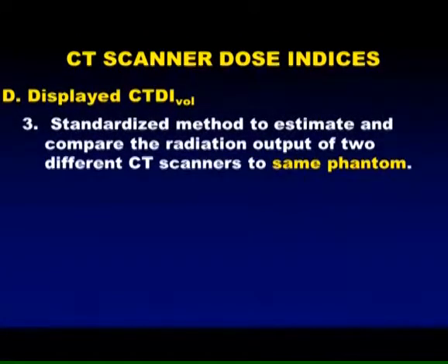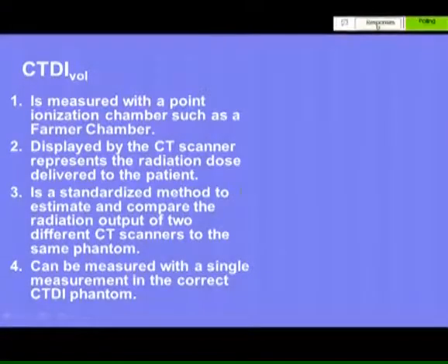So CTDIvol is just a standardized method to estimate the radiation output of two different scanners to the same phantom. It does a beautiful job of doing that. That's what it was defined to do, and that's all it was intended to do when Tom Shope and others at the FDA defined CTDI a number of years ago.